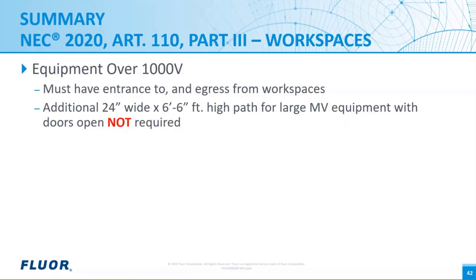And that is going to be possible if they determine that this rule was inadvertently left out of medium voltage installations and should have really been applied there. But since large equipment greater than 1,000 volts has control compartments with low voltage, does this mean we automatically have to assume that we're back to the new rule in 110.26(C)(2)? I personally don't believe that was the intent, but that is my opinion, and it's really going to be up to the proper authority having jurisdiction to determine these types of issues.